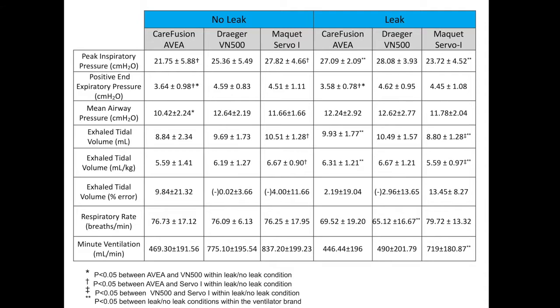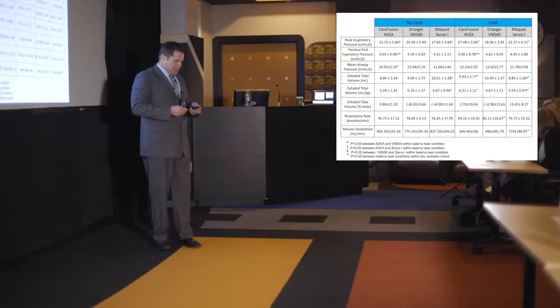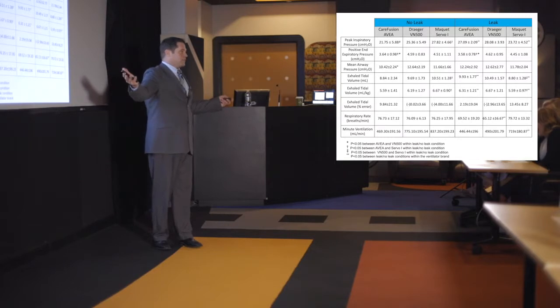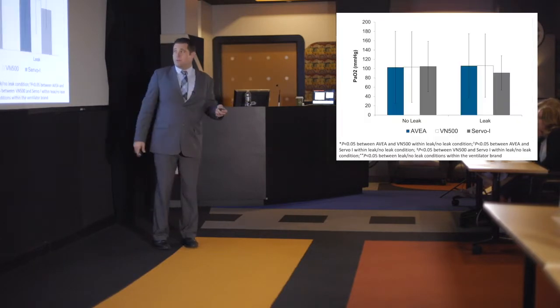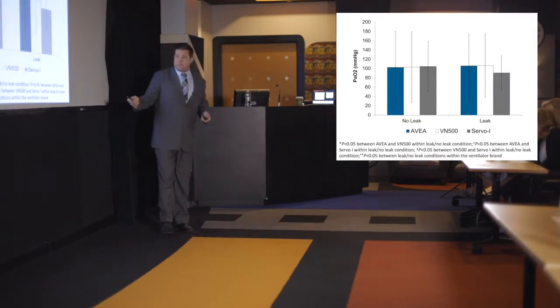If you look at these pressures after you implement an endotracheal tube leak, this is pretty fascinating. The pressures go up with the Avea because it's basing its adjustment and pressure on a leak. And if we see here with the Draeger VN, it's adjusting its pressure based on a leak. But here with the Maquet Servo-i, the pressures are actually being weaned down, based on that inspiratory volume. And really, this is helpful for any ventilator manufacturer, to show that it's probably not an awesome thing for them, especially if they have an ET tube leak.